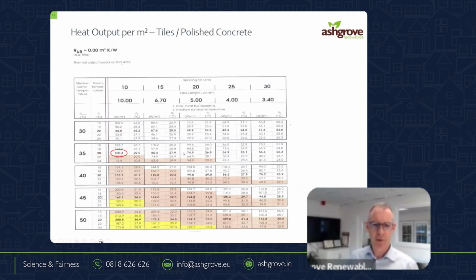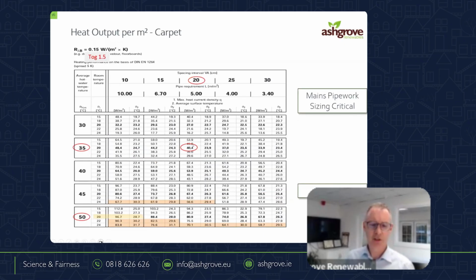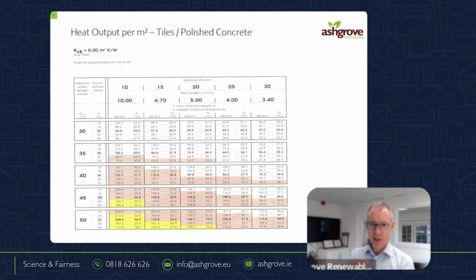Okay, so you can see there actually, in this case, if I go back one, you can see that actually doubling up on the pipework here, I've put in the pipes at 20 centimeter spacing, so I get 40 watts. You'd think by doubling the amount of pipework, I would get double the amount of heat. I don't. I actually only get 20%. Right? The floor is now saturated. You can put in as much as you want after that. It doesn't affect it anymore. Point being, I suppose this is one of the reasons we hear about heat pumps giving trouble all the time, and in this case, is fully within our control.